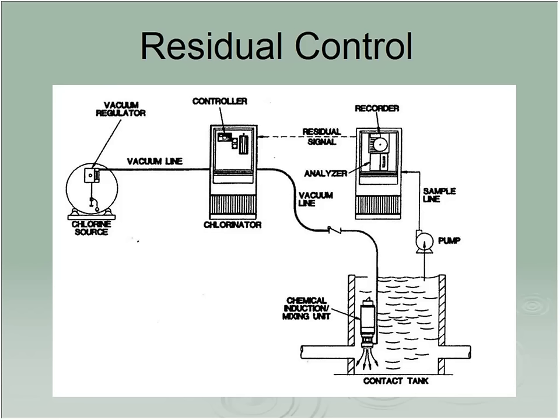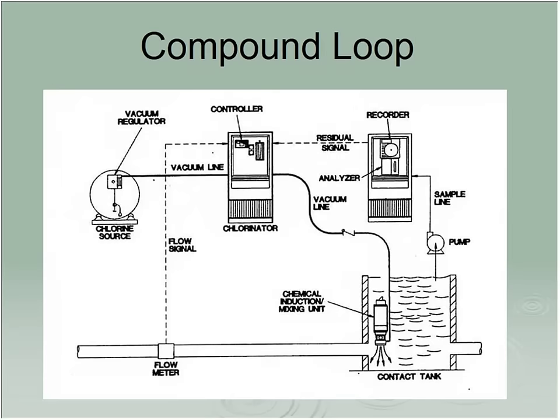Maybe you get a little upset in your clarifier, something like that. Stuff could go by that you wouldn't have enough there. We can do a residual chlorine. We're actually going to sample after our treatment with the chlorine, which is a 30-minute delay time, and say, okay, I want to have so much of a residual, and that's going to tell it how much chlorine to add into the system.